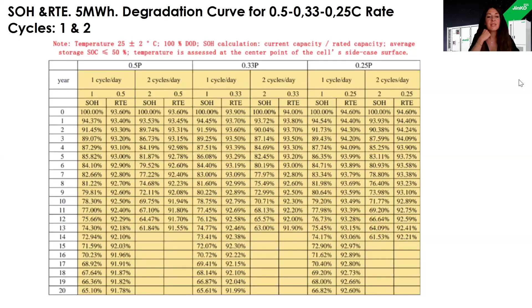Which means 2 hours for 0.5C, 3 hours for 0.33C, and 4 hours for 0.25C, for example with 1 cycle a day. Here you can see from year 0 up to year 20, we would say the SoH up to 60% is the maximum we can guarantee the battery will perform appropriately. So here you can see, for example with 2-hour charge-discharge with 1 cycle per day, we will reach in year 20 an SoH of 65.10%, which is quite interesting data.